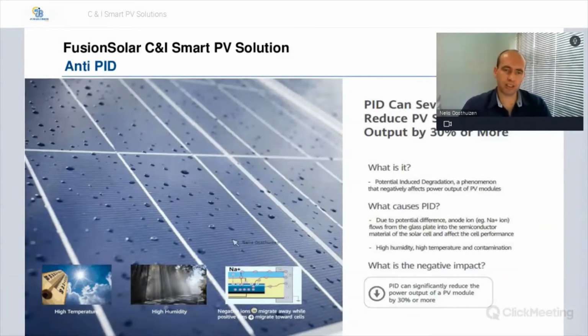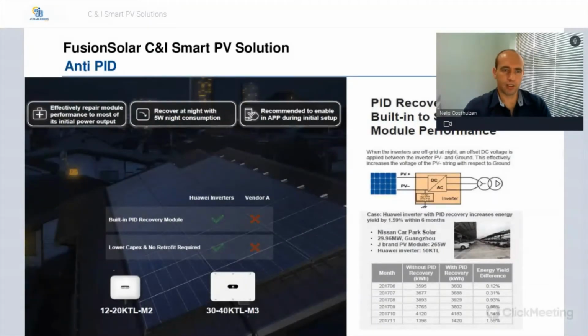Most of the modern tier 1 PV modules will state that their panels are immune, or that there won't be any PID effect on them, but definitely there is some PID effect that can occur. But Huawei has got their own solution for AntiPID. If we move over to the next slide, it's just a comparison between Huawei inverters and a certain competitor. Huawei inverters have a built-in PID recovery module, and because it's built into the inverter, there's no need for extra equipment. So this lowers your capital expenditure, and there's no retrofit required.